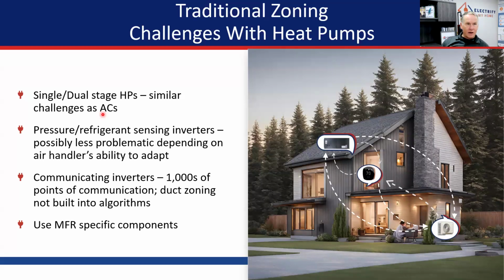And what we've seen a lot, and I've seen it because other customers have shown me the quotes, is people putting in a communicating system. They put in 24-volt control interface modules, so the thing runs on 24 volts, and it basically takes all the communication out of the thermostat, and then they run that through zoning. That still does not do it. Now we've got three things in there that aren't talking to each other instead of just two.